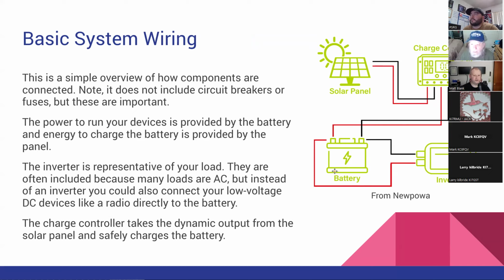This chart doesn't include any circuit protection, unfortunately, but it should be pretty much everywhere in here. Usually inverters will have their own, but it's really best to have a fuse as close to the battery terminal as possible to prevent any downstream issues from short circuiting.